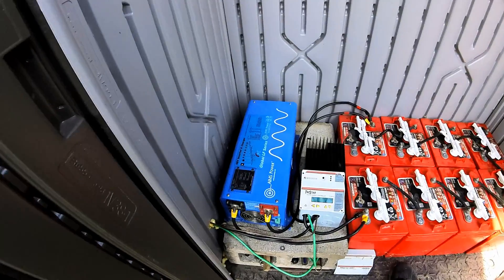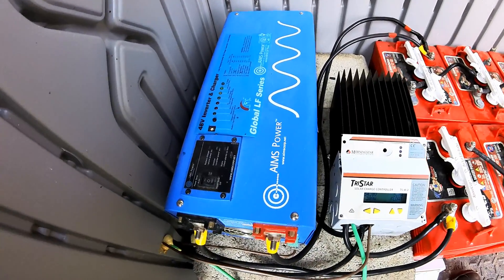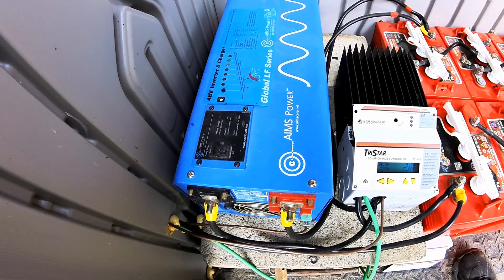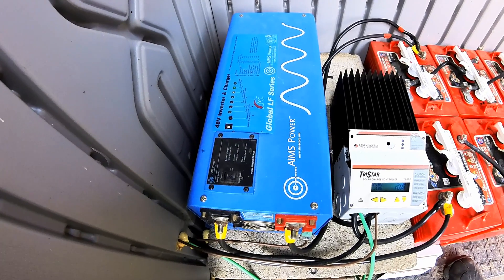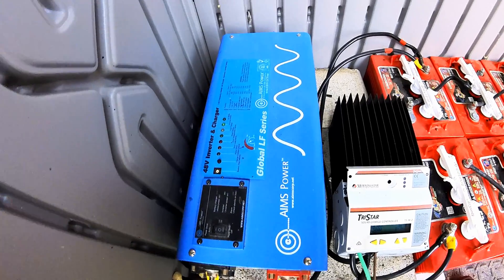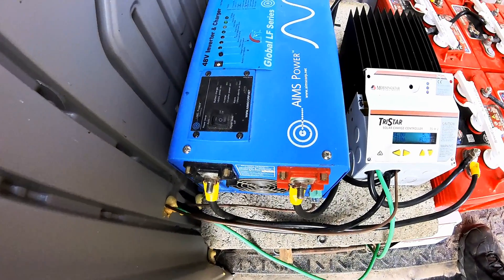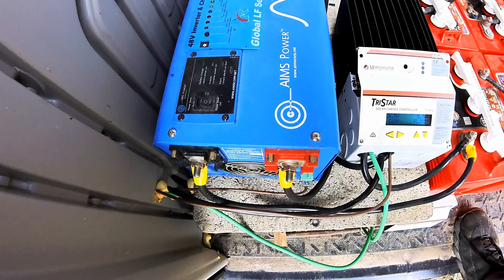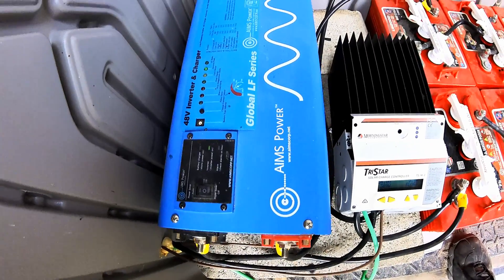Back over here to the battery shed — I've shown the system a couple times but let's go over it quickly. This is an AIMS Power inverter, a 48-volt inverter because we're running the system on 48 volts. AIMS also makes 24-volt and 12-volt inverters. Being a 48-volt inverter, it's also an inverter charger, meaning it's capable of actually starting up a generator. It has a self-start where it can start a generator and back-charge your batteries if the sun isn't able to do its job. It's a smart inverter charger — it will also charge the batteries once it starts the generator.